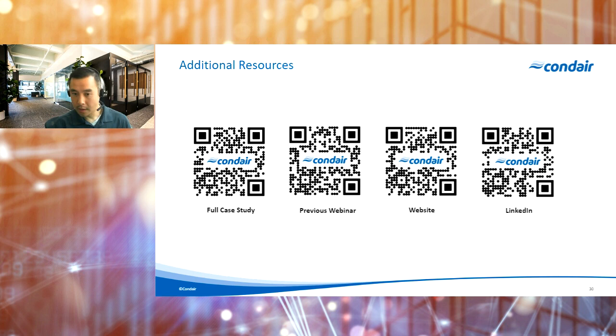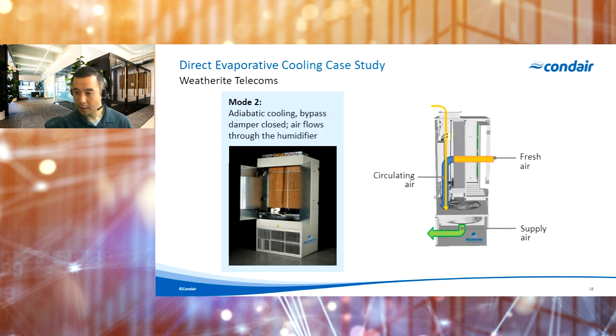Well, I can start. So there was a question: is the media replaceable because of hard water or contamination? In general, yes. It's a little bit specific to the air handler OEM who is making it. Though generally the media lasts about 5 years, so there is an expectation, typically almost always, to replace the media multiple times throughout the life cycle of the air handling unit.